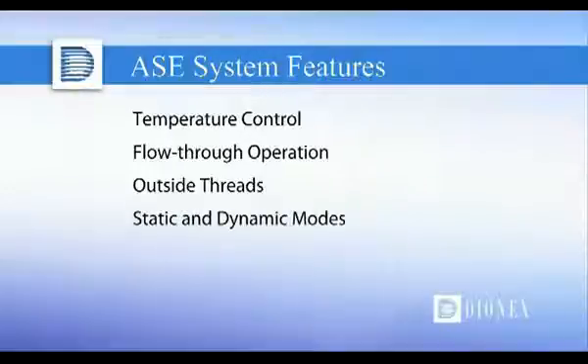ASE systems also feature superior temperature control of cells, flow-through operation for in-line filtering and cleanup, cells threaded on the outside for ease of use, and the capability of static or dynamic extraction modes operating separately or concurrently.